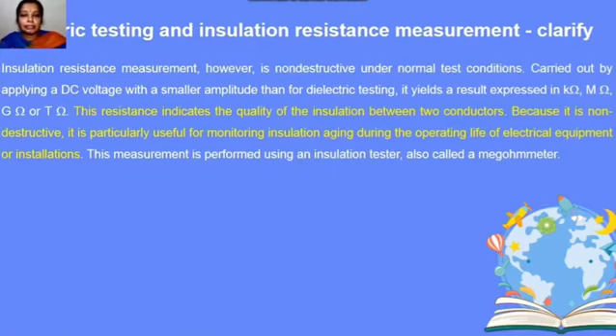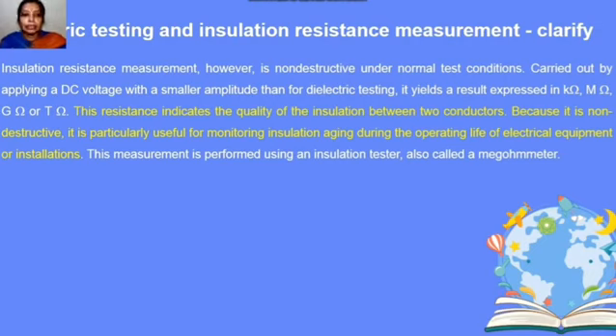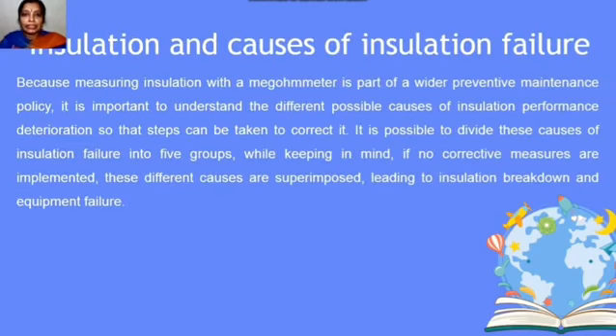Insulation resistance testing, however, is a non-destructive test. A DC voltage of relatively lower magnitude is applied, and the result is in kilohms, megaohms, gigaohms, or teraohms. The resistance indicates the quality of the insulation between two conductors. Because it is non-destructive, it is practically useful for monitoring insulation aging during the operating life of electrical equipment. The measurement is performed using an insulation tester, also called a megaohm meter or megger.